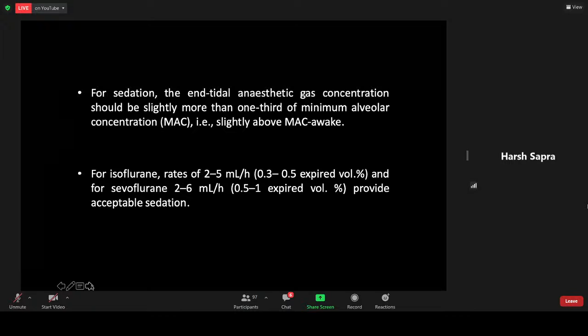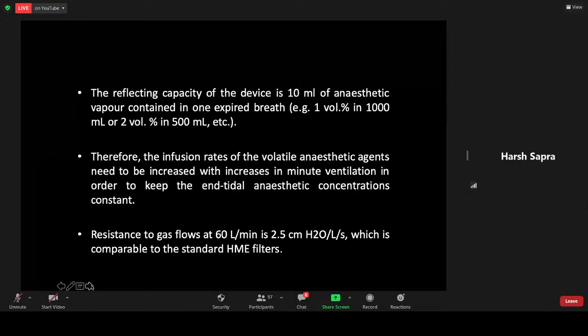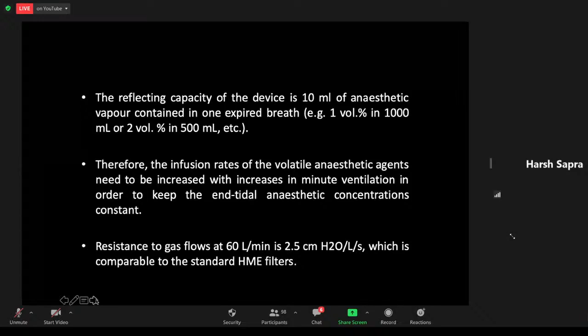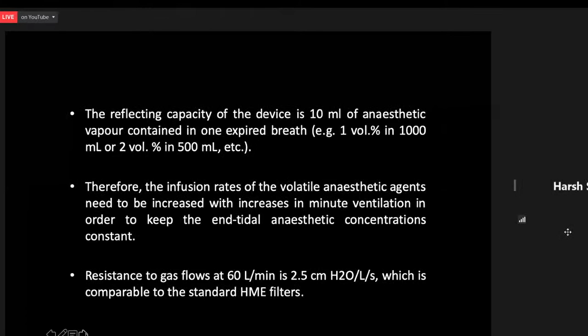The reflecting capacity of the device is 10 ml of anesthetic vapor contained in one expired breath, so of approximately 1% volume. Therefore, the infusion rates of the volatile agents need to be increased if the minute ventilation is increased, and the resistance is not more than any other standard HME filter available in the market.